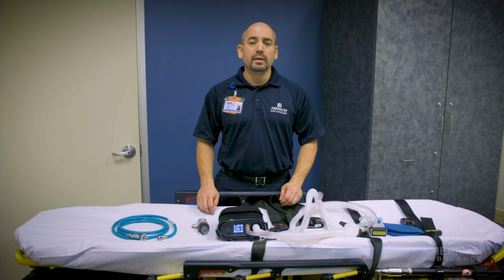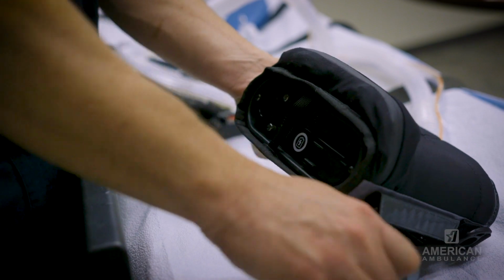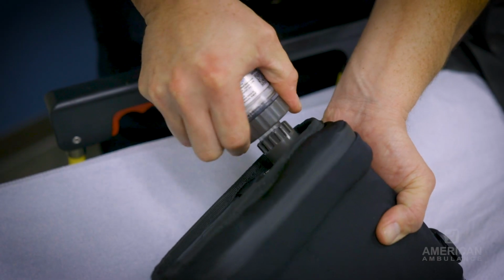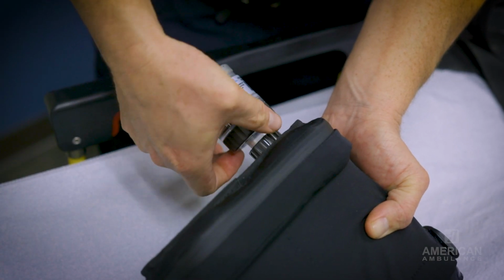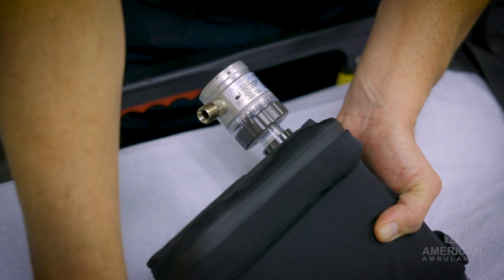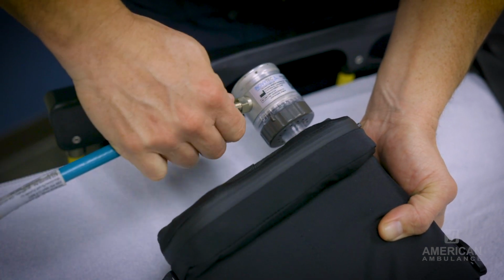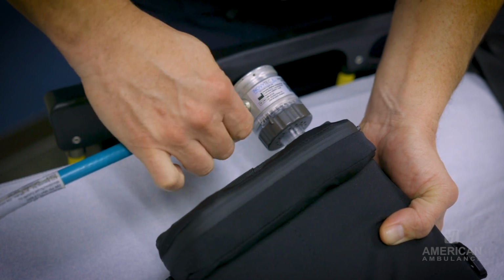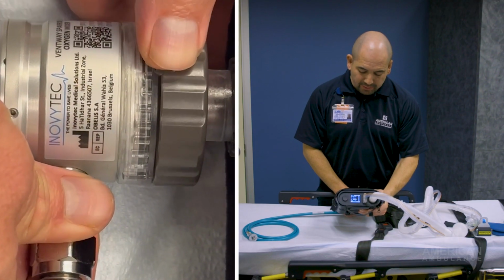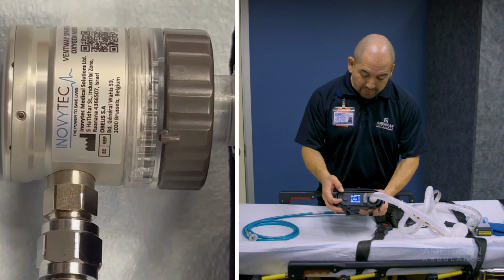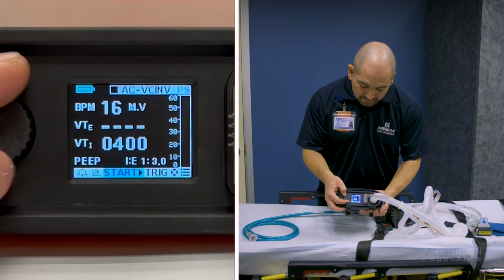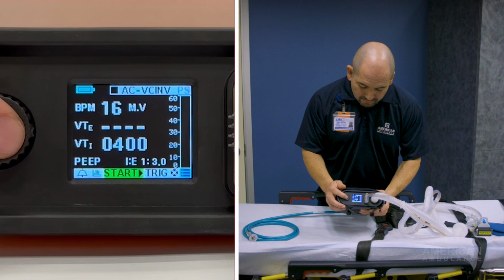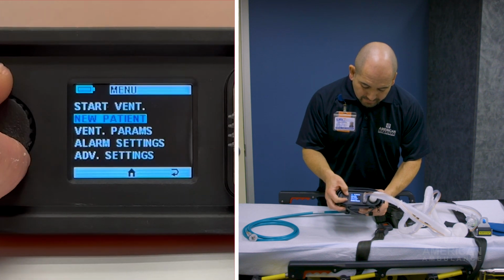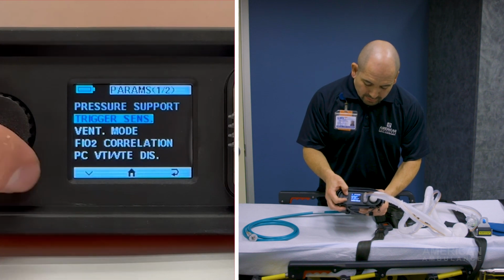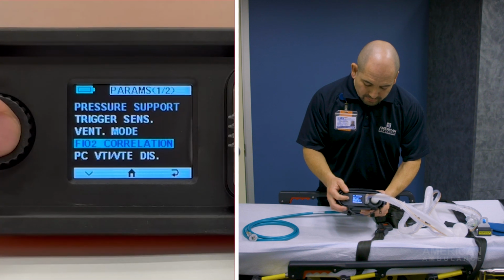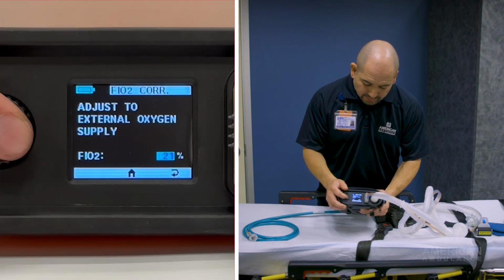The last step is to hook up the oxygen. Plug in the oxygen blender into the back of the vent and secure it with 2 turns. Plug in the high pressure oxygen tubing to the oxygen blender. Adjust the FiO2 to 60%. On the ventilator screen, navigate to the menu, select vent parameters, select FiO2 correlation, and adjust to 60%.